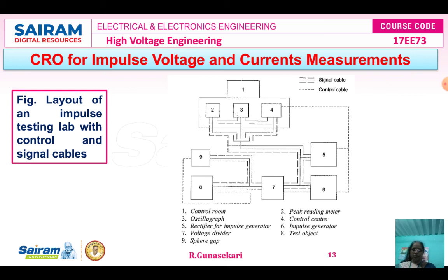It is extremely difficult to control and adjust the impulse wave for different load conditions, as in the case of large capacitive loads, very low inductance coils, and transformers with high inductance and capacitance. Further, whenever the test requires comparison of test records, the resolution and uncertainty in measurements will affect the test result, and the records should be capable of detecting even small deviations or changes.